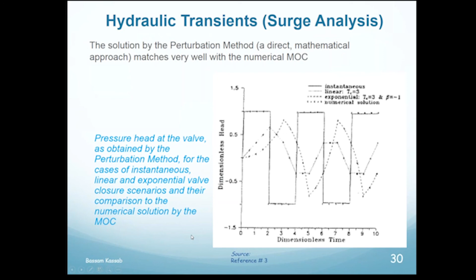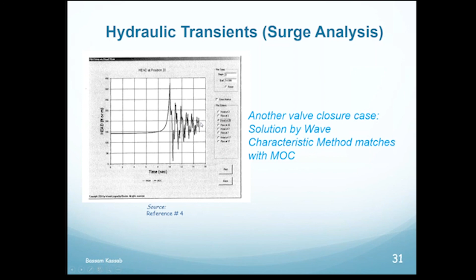And when you do exponential closure for the valve, you can even get less transient. But you'll always get some transient when you're closing a valve. That's why my advice is to always close the valve slowly. And here from a software, it's showing what the software does versus the method of characteristics, that they have a good match. And here's a different case than the one I showed you earlier. It's not just a valve closing, but you can see how the transient oscillates, and the pressure could go up and down, up and down, up and down, until it subsides over time.